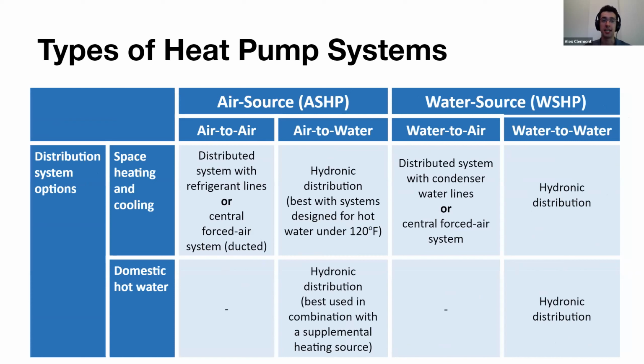Usually an air source machine is air to air, where the outdoor machine is extracting heat or ejecting heat to the outside and then delivering it to the space with refrigerant lines at the ductless or ducted central unit. Now it can also be air to water, which we won't talk about too much today, but in that case, you're actually delivering water to the space. Now, a water source heat pump is usually known as water to air, where you have a condenser water loop in a building and you have a bunch of water source heat pumps that heat or cool the air.